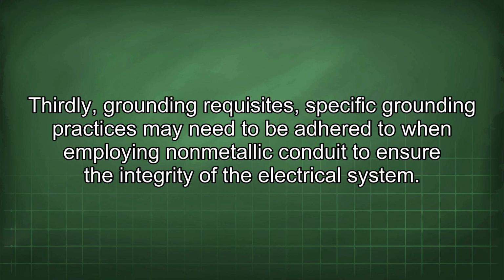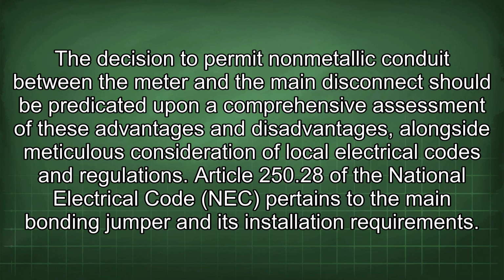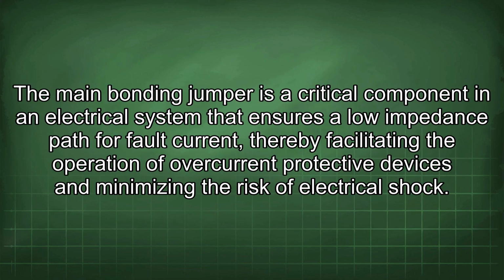of the electrical system. The decision to permit non-metallic conduit between the meter and the main disconnect should be predicated upon a comprehensive assessment of these advantages and disadvantages, alongside meticulous consideration of local electrical codes and regulations. Article 250.28 of the National Electrical Code (NEC) pertains to the main bonding jumper and its installation requirements. The main bonding jumper is a critical component in an electrical system that ensures a lower impedance path for fault current, thereby facilitating the operation of overcurrent protective devices and minimizing the risk of electrical shock.